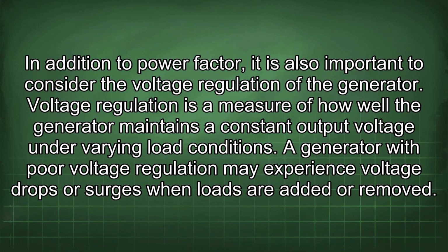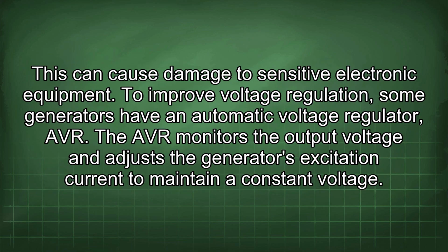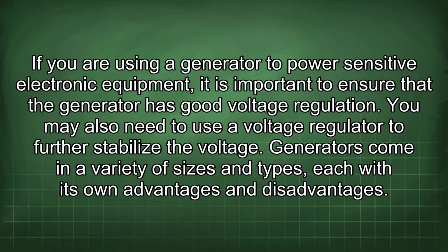Voltage regulation is a measure of how well the generator maintains a constant output voltage under varying load conditions. A generator with poor voltage regulation may experience voltage drops or surges when loads are added or removed. This can cause damage to sensitive electronic equipment. To improve voltage regulation, some generators have an automatic voltage regulator, AVR. The AVR monitors the output voltage and adjusts the generator's excitation current to maintain a constant voltage. If you are using a generator to power sensitive electronic equipment, it is important to ensure that the generator has good voltage regulation. You may also need to use a voltage regulator to further stabilize the voltage.